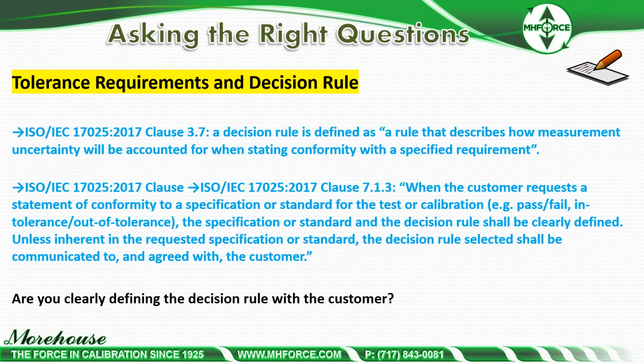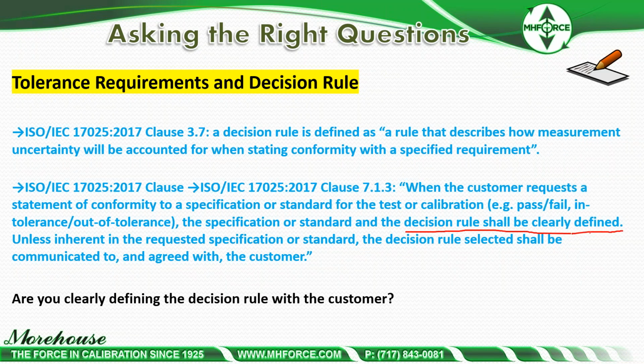And then we have 713. When a customer requests a statement of conformity to specification or standard for the test, calibration, pass, fail, in tolerance, out of tolerance, the specification or standard, and the decision rule shall be clearly defined. This can be simple acceptance, but you have to have the discussion. And if you don't have the discussion, I have a little bit of guidance here. And my question is, are you clearly defining the decision rule with the customer?